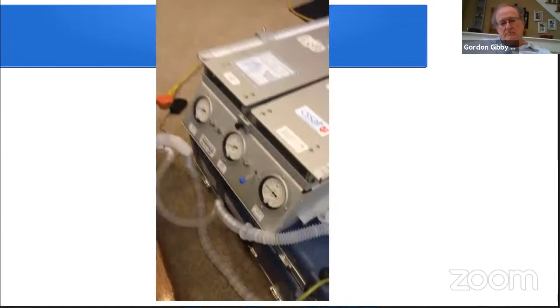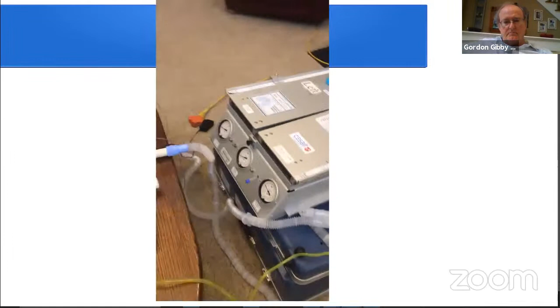And it is going to hunt with an algorithm to try to bring that number up, and it takes it a few breaths to get there. And it has some algorithm, so if it overshoots, it makes quick corrections, but it will gradually get us right to 10 centimeters and stop. And we were astonished at the accuracy that we developed. We were within 1 centimeter of water, which is not much pressure difference. It's already hit 10 centimeters. So that shows you the 2 control mechanisms that we used in the system, and we spent 2 weeks developing control systems, and we're not done yet. Okay?